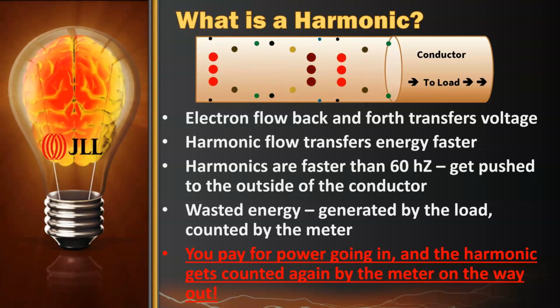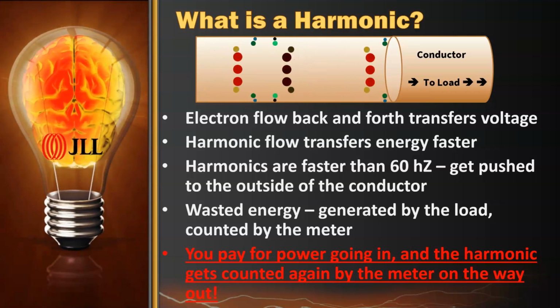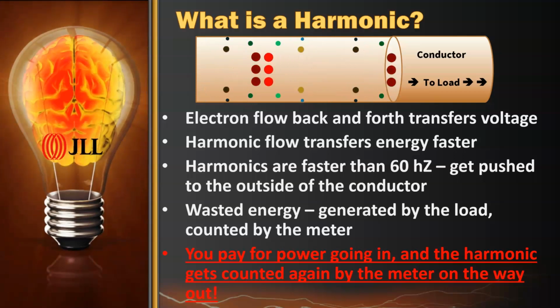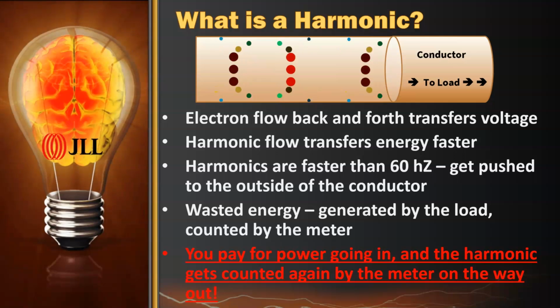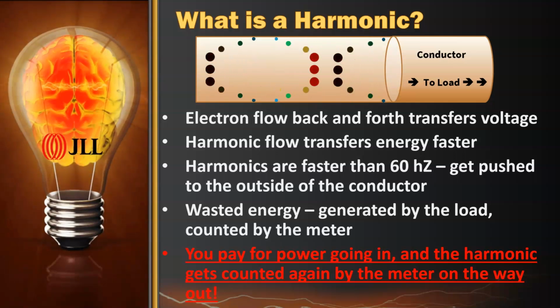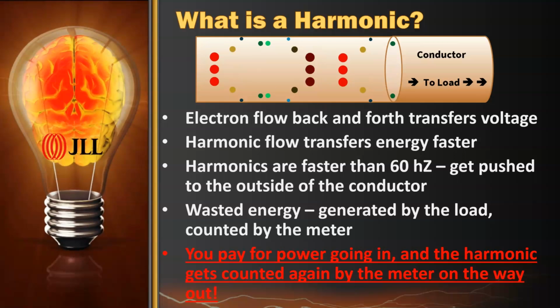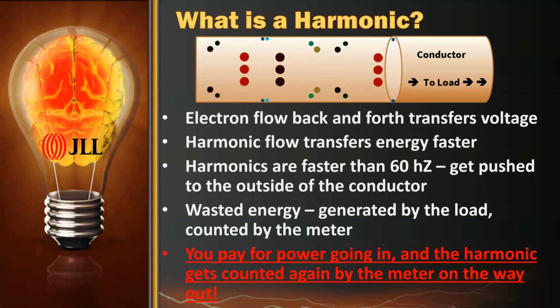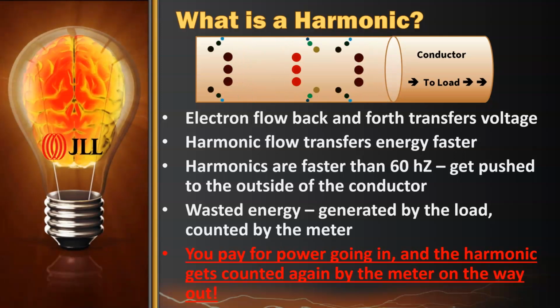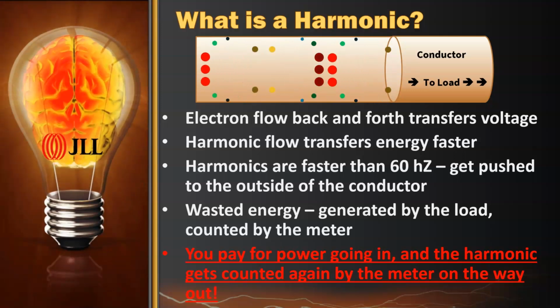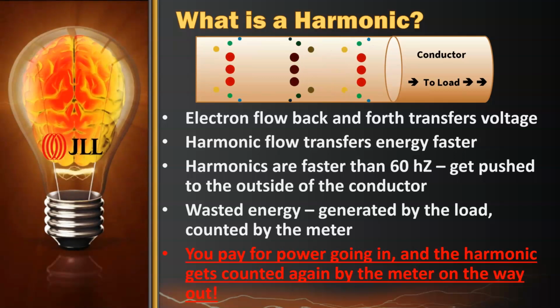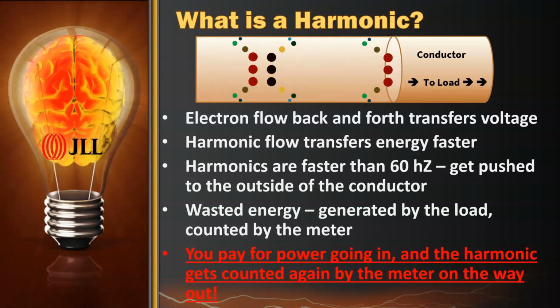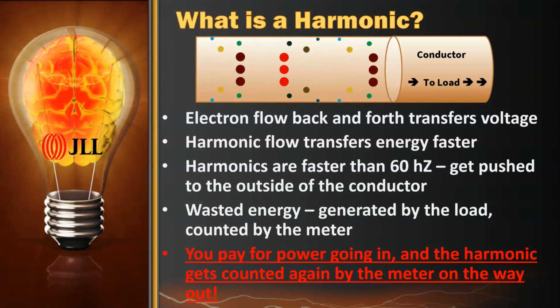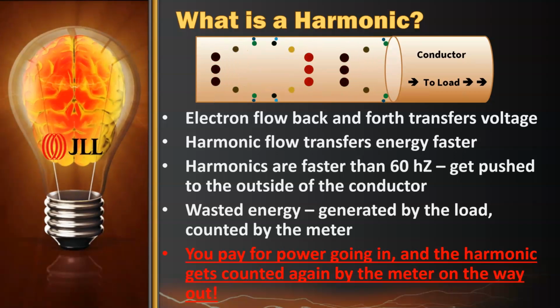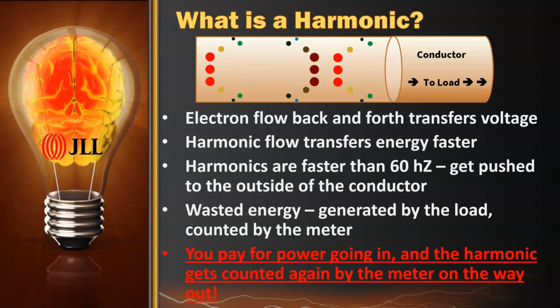And you can see them getting pushed to the outside of the conductor. So think about that conductor for a minute. It's a solid piece of copper, and what's happening is the electrons inside that copper are moving back and forth at different rates down the length of the copper conductor. Not surprisingly, what happens to that conductor is it tends to physically vibrate. And that's the buzzing sound you hear when there's a high harmonic.